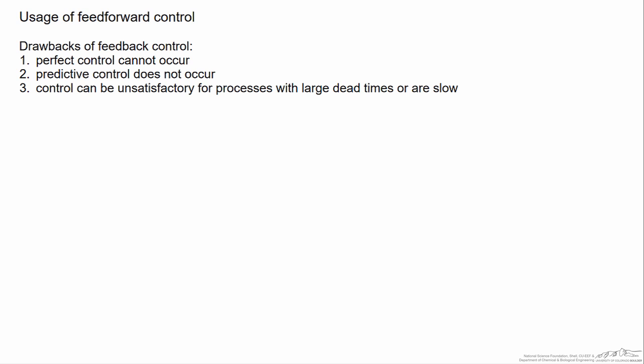Because you are only measuring the controlled variable at the end of the process, there is no way to predict what is going to happen to this variable. An additional problem is that processes are slow or have large dead times, which can lead to control that will take a while. If a system has a very large dead time, the disturbance will occur, the process won't feel it for a while, but once it feels it, it will take a while to actually act on it because of the slowness of the process. So feedforward control is a way to handle all three of these drawbacks.